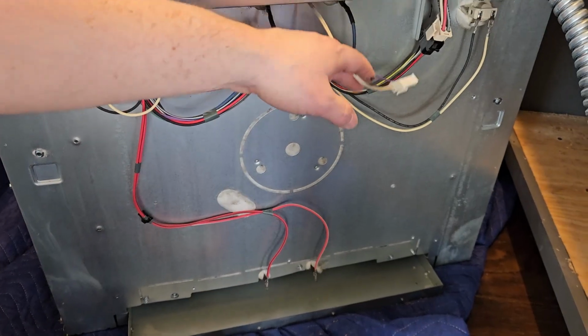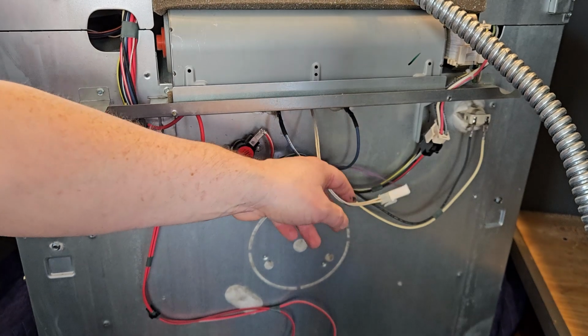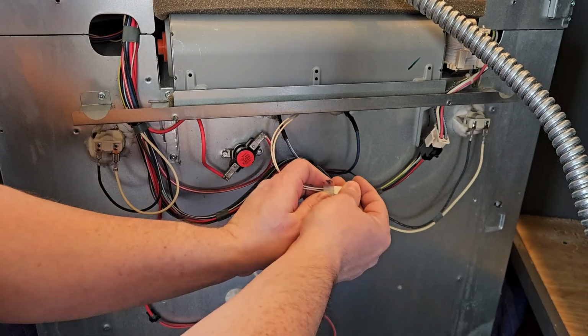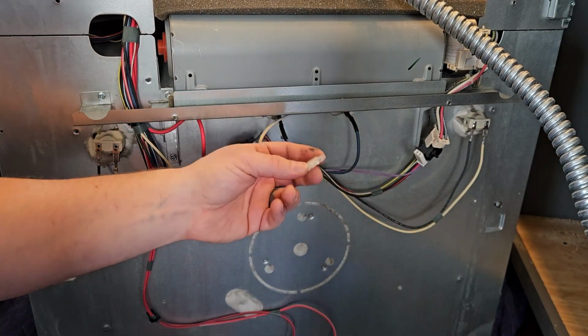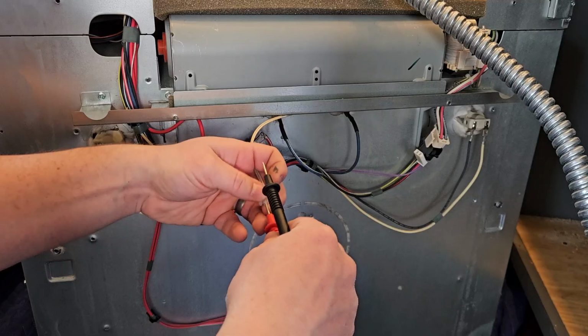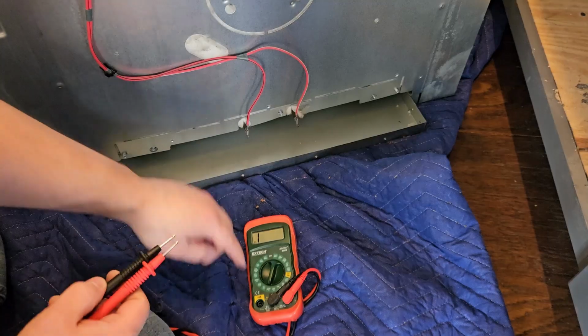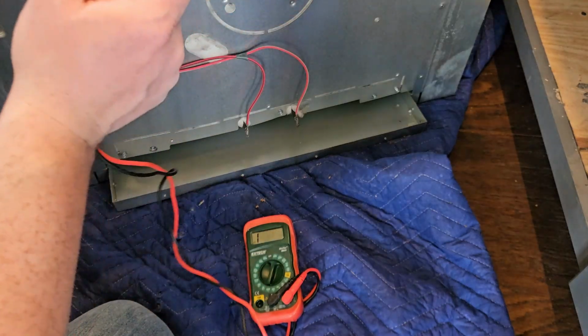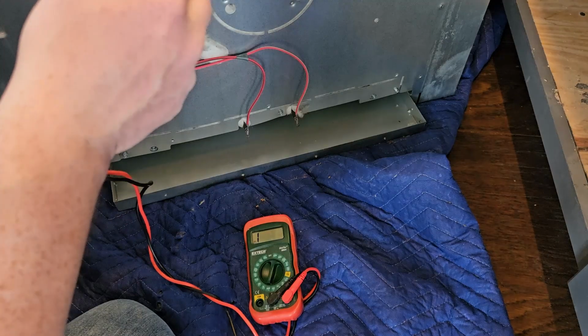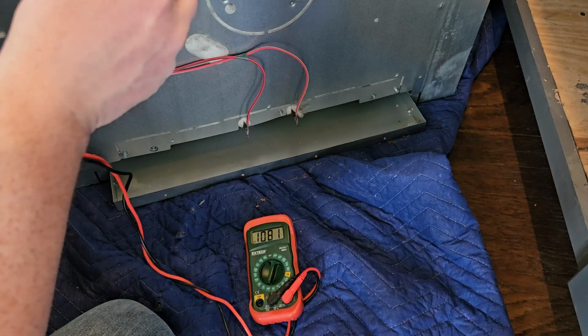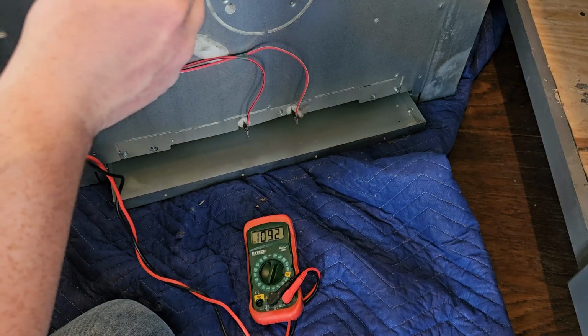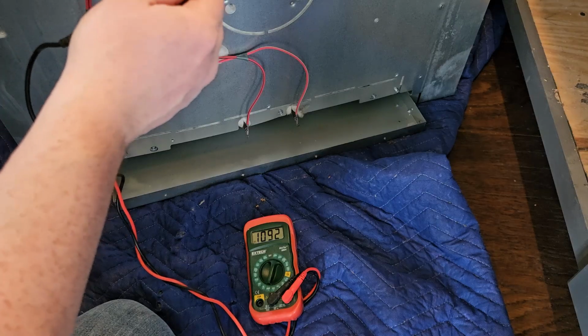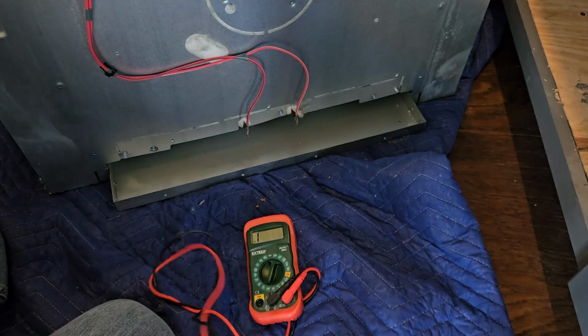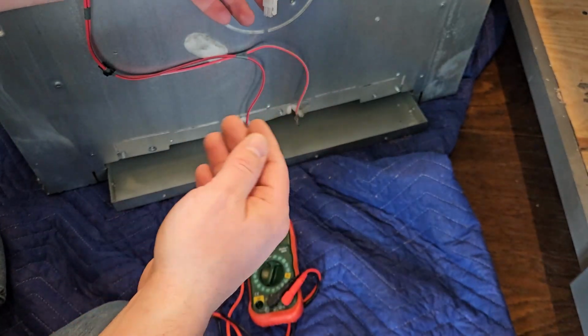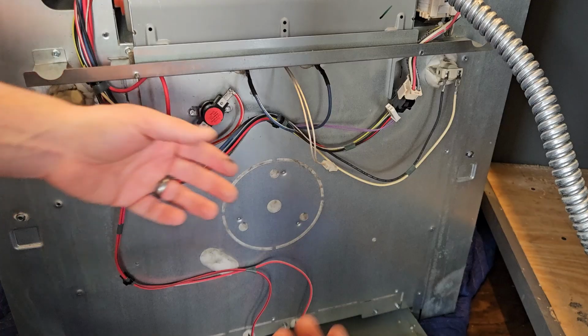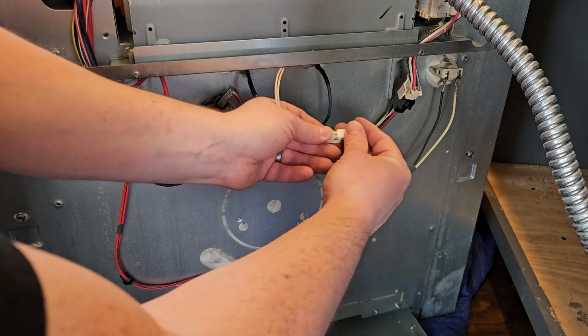You can expect for this top thermistor, it's probably going to be around 1100 ohms if it's a good reading. Just unhook that and set these in. I've got it set to the 2000 ohm setting because I'm expecting it to be around 1100 ohms. And look at that, 1091. That is a good reading for this temperature sensor at room temperature. It will change if the temperature sensor is hotter or colder. So it's not the temperature sensor. We'll close that back up.